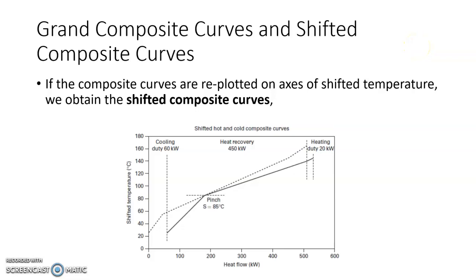In this video we are going to discuss grand composite curves. First, let us look at the shifted composite curves diagram. If we plot the shifted temperature and corresponding enthalpy, we get shifted composite curves. The basic difference between shifted composite curves and the actual temperature composite curve is that at the pinch point both curves touch each other. On an actual temperature scale there would be a difference of delta T minimum, but for shifted temperature both hot and cold streams are touching at the pinch point, whereas actually they are delta T minimum apart.